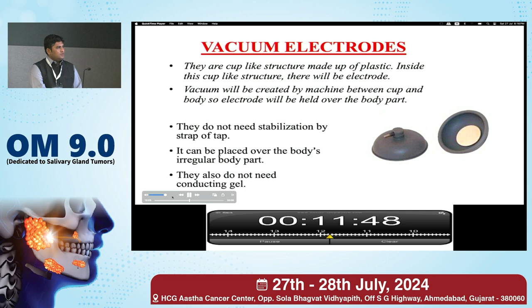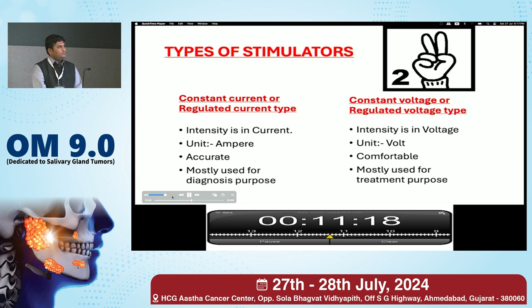Now coming to the types of stimulator used for electrotherapy. The 2 types of stimulators used are constant current or regulated current type and constant voltage or regulated voltage type. Constant current type, the intensity is in current, that is amperes. They are more accurate and mostly used for diagnostic purposes. Constant voltage type, in contrary, the intensity is in voltage. They are more comfortable and most commonly used for treatment purposes.